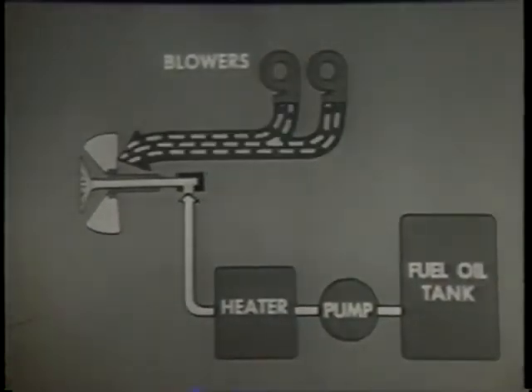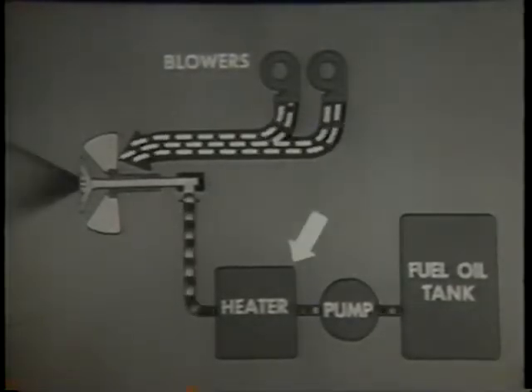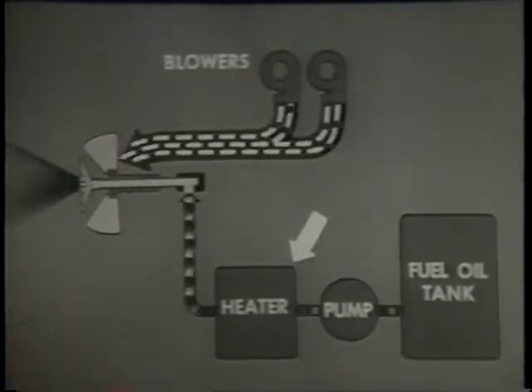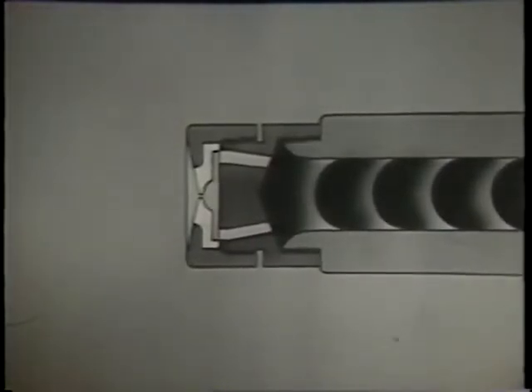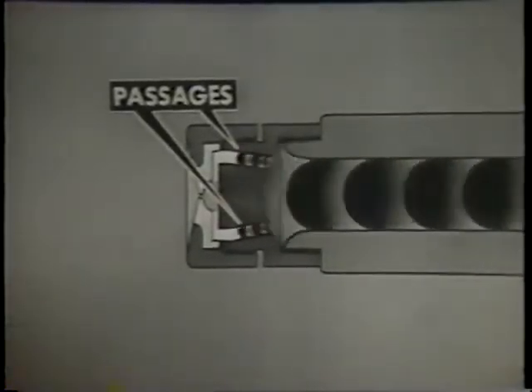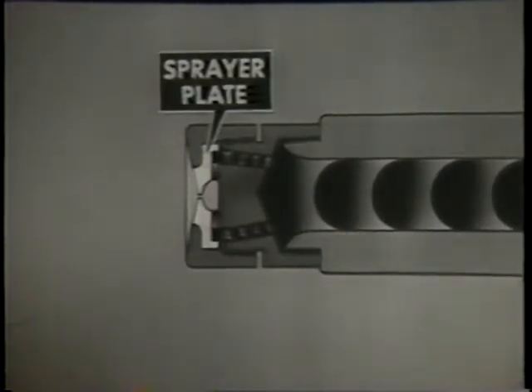The force draft blowers send a strong blast of air to the burner. The fuel oil pump sends the oil through the heater where the oil is heated to give it good flow qualities, then the oil is pumped to the burner. This simplified cutaway of the burner shows how the fuel oil is forced through the burner barrel to the atomizer nozzle, where a series of passages guide the oil to the sprayer plate. The sprayer plate makes the oil rotate at high speed, breaking up the oil into particles. The oil leaves the atomizer as a hollow, mist-like cone or spray.